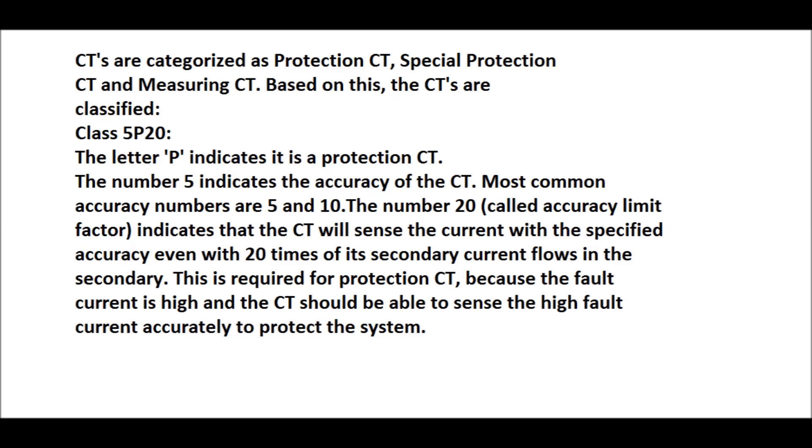The number 20, called the accuracy limit factor, indicates that CT will sense the current with the specified accuracy even with 20 times of secondary current flows in the secondary. This is required mainly for protection CT because the fault current will be as high as beyond 20 times during fault conditions. Therefore, accuracy protection of CT is required.